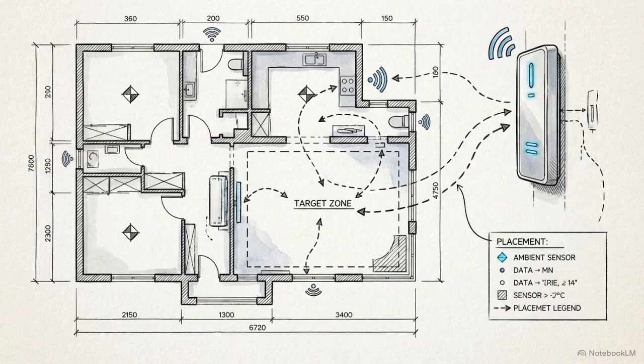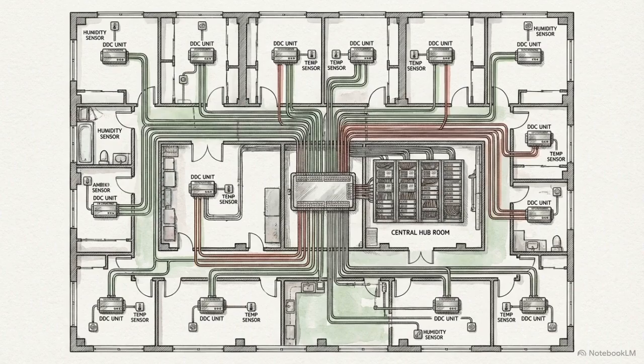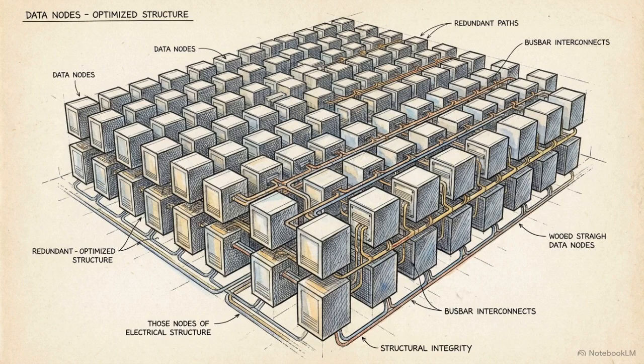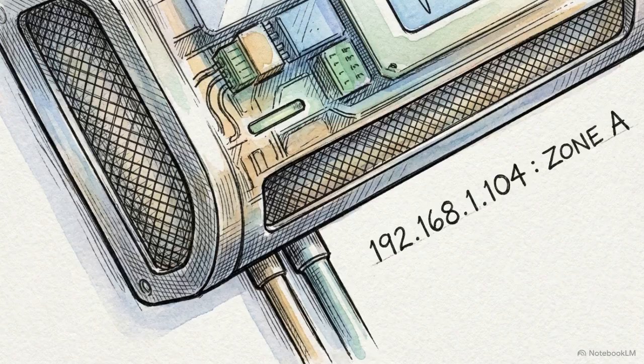Here, engineers select the specific field sensors and DDCs and map out the exact communication network topology required to link them. During this phase, they must architect a rigid database structure. Every single piece of hardware requires a unique digital address, so the server knows exactly where incoming data is originating.